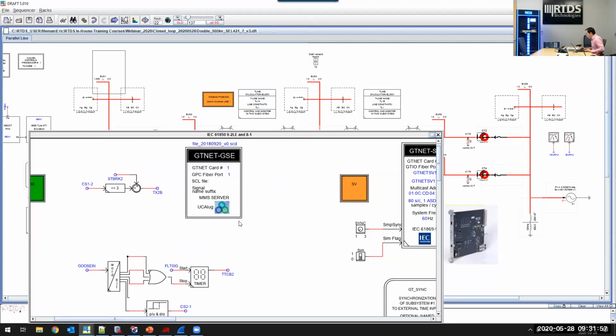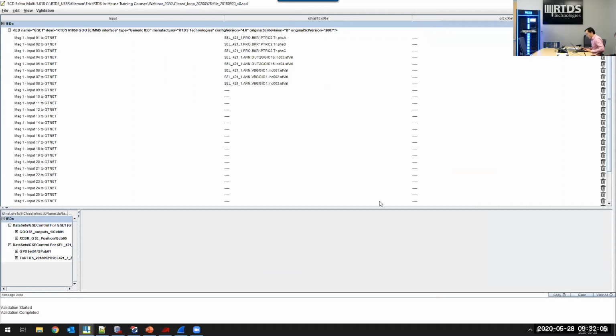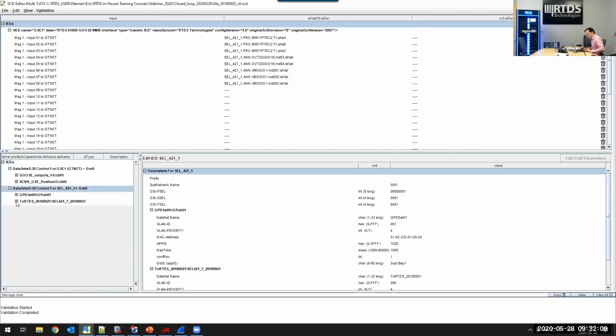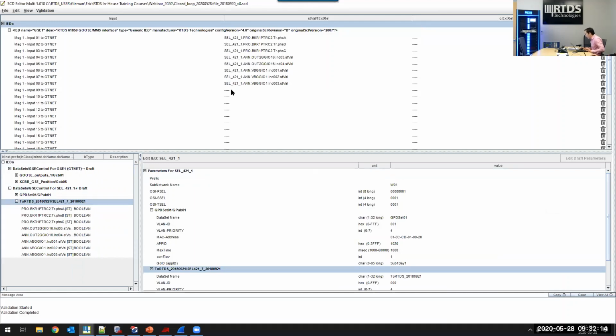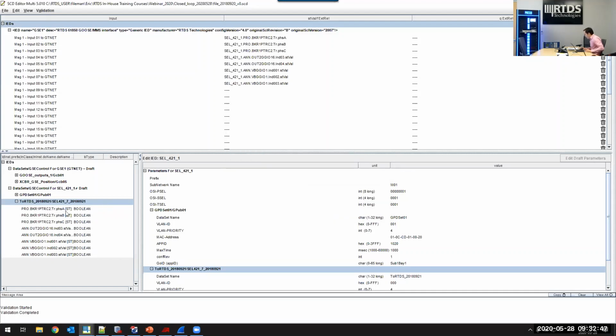For GTNet Goose input configuration, we need to go back to this editor. Firstly, we need to import the configuration file that contains the Goose output information of the external relay. Later, we will touch on the process of how such a file is generated in the relay's configuration tool. For now, assuming that we have the file ready, the file can be imported by going through File, Import. Then select the target file. In this demo, it is this SELCID file. Once the file is imported, as I did already, the relay's Goose output data set would be shown below the GTNet IED, under the IED section here.